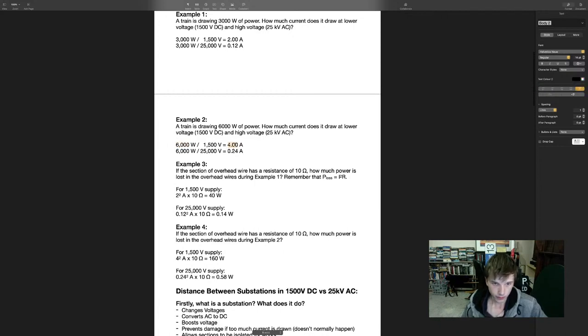4 amps for the lower voltage system and 0.24 amps for the higher voltage system. Plug those numbers in - now you're really seeing a big difference. We've doubled the current and quadrupled the power lost in both examples. I know that 0.58 isn't exactly 0.14 times 4, but that's because of rounding errors. Trust me, the true power loss is double.